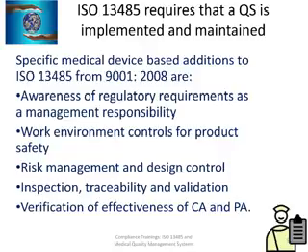But they've increased it, or I should say raised the bar, in terms of awareness of the regulatory requirements as a management responsibility. And then they have tighter work and environmental control for product safety, because most of the devices we are talking about, for which ISO 13485 is applicable, get implanted in people or used on people, so product safety and efficacy is extremely important. Okay? And of course, risk management and design control are a bigger aspect in 13485 as compared to 9001. They have stringent standards for inspection, traceability, and validation, as you'll know.